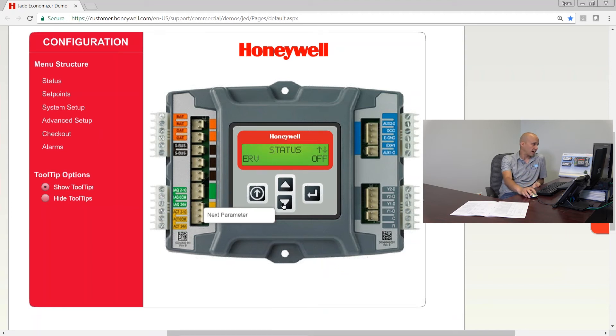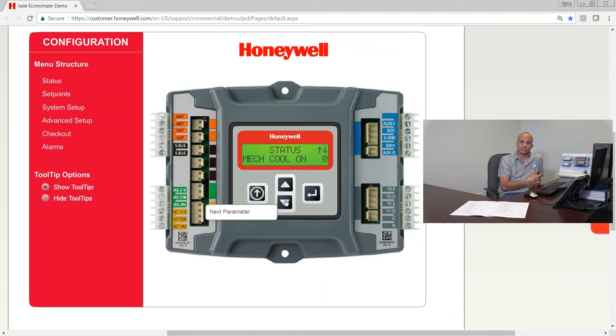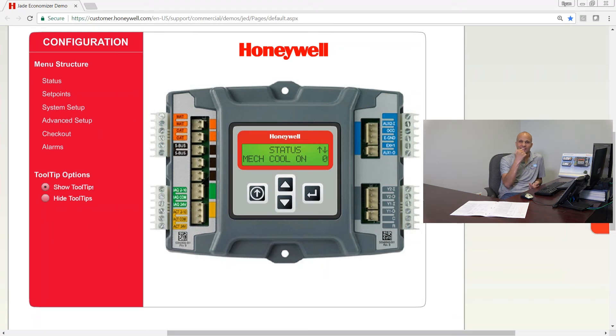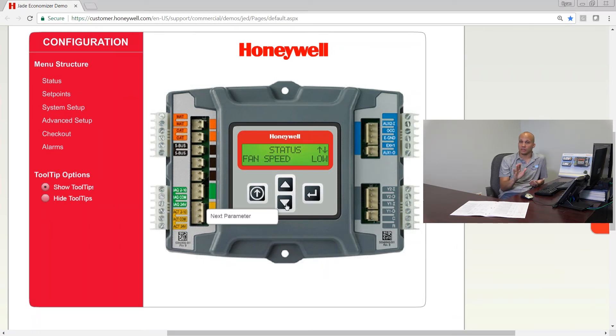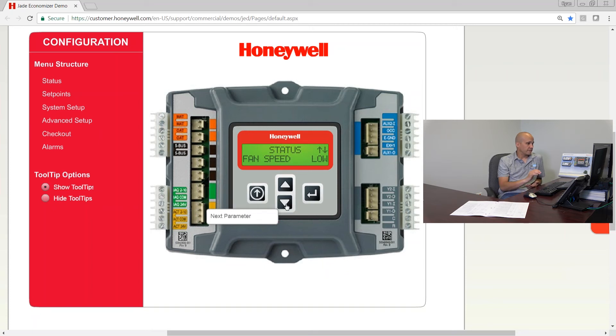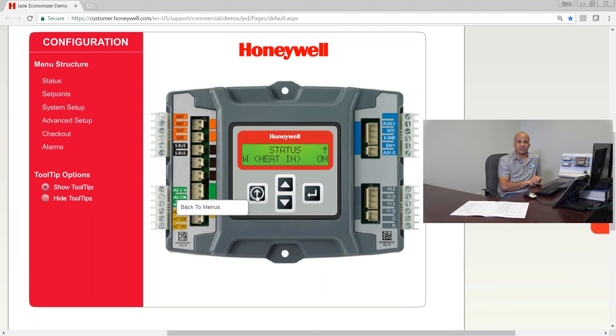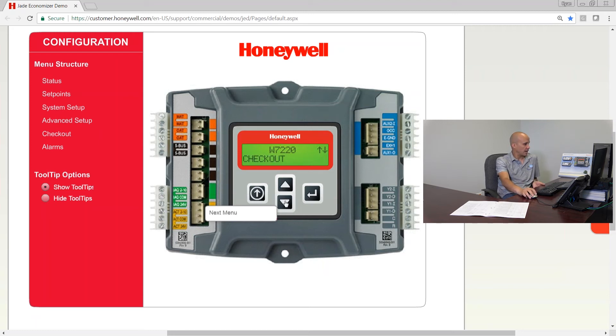Exhaust fan one out: if my controller is telling the exhaust fan to turn on, this will change from off to on. Exhaust fan two out covers a second stage if I have a two-stage exhaust fan. If I have an optional ERV wired to here, which is rare, it would tell me if it's being commanded off or on. Mechanical cooling shows zero, one, or two — zero meaning no mechanical cooling, one being first stage, two being second stage. The last couple items are fan speed low or high, minimum damper position for a two-speed fan system, and W heat in — if I'm getting a call for heat on a two-speed fan system, that would display here. That covers all the status screens.